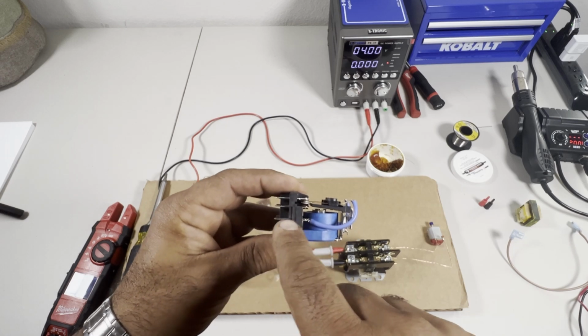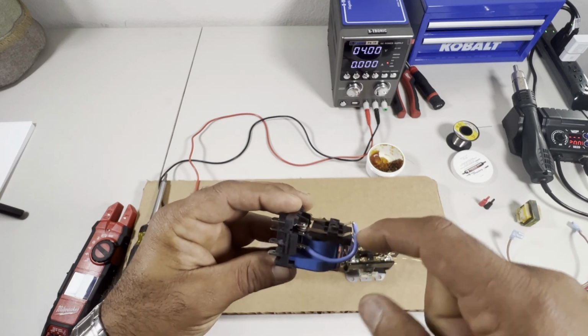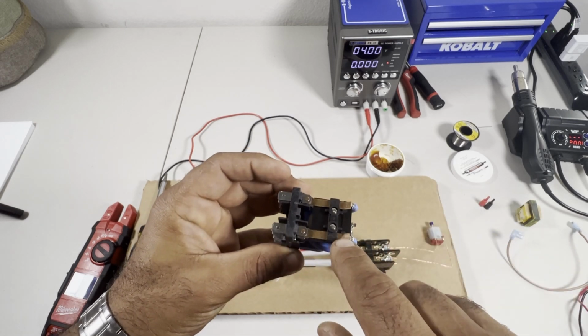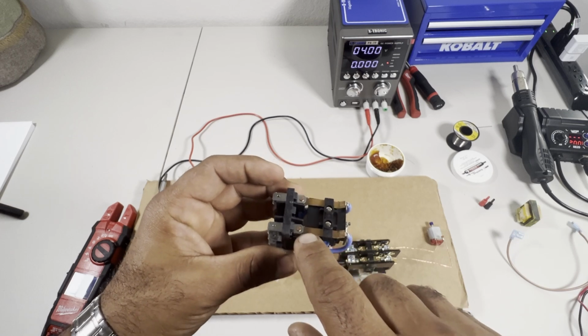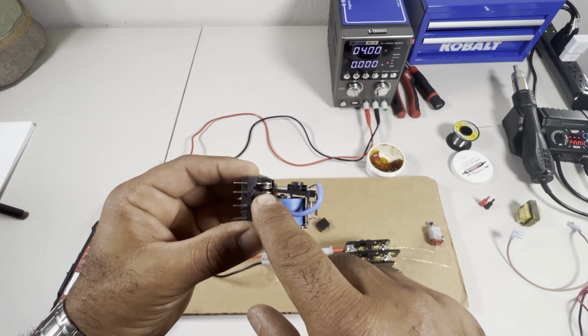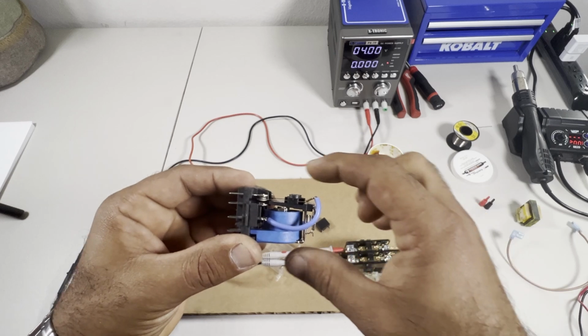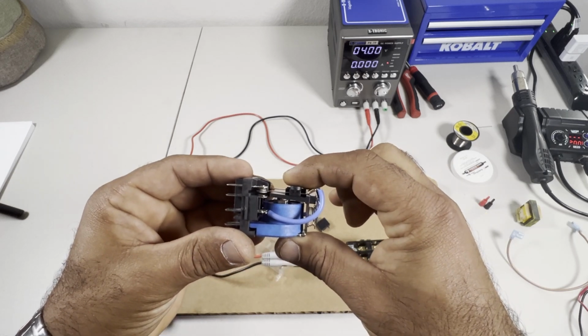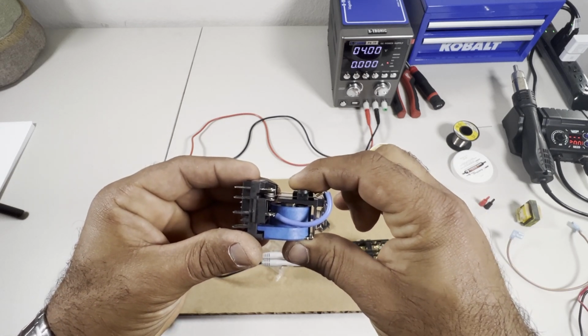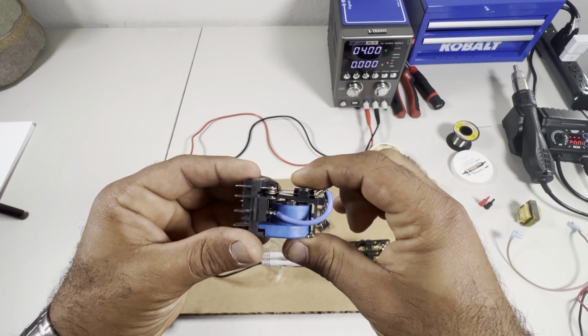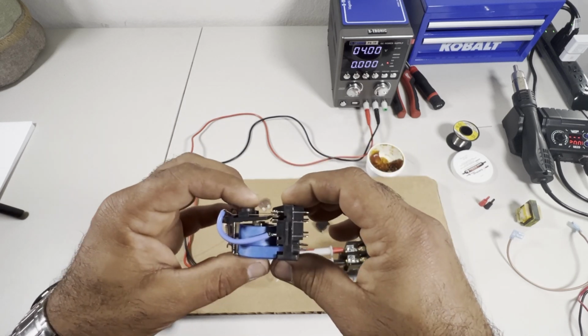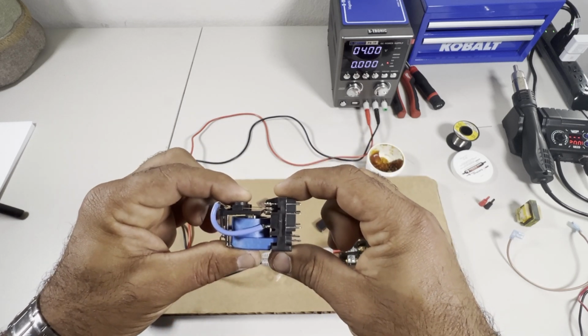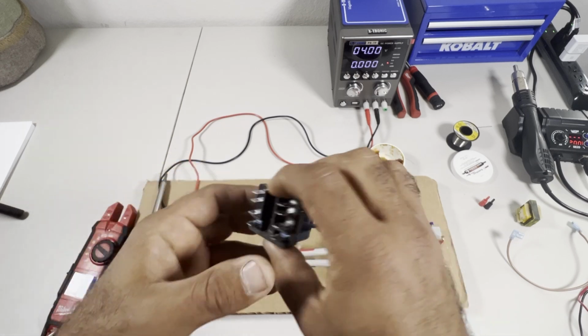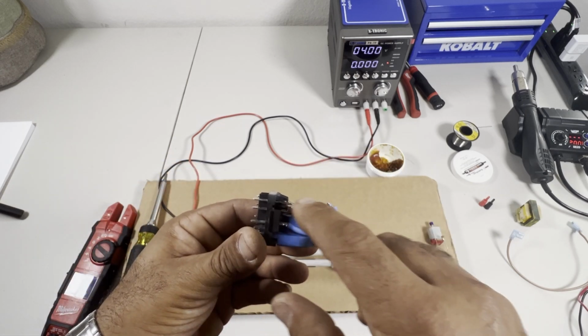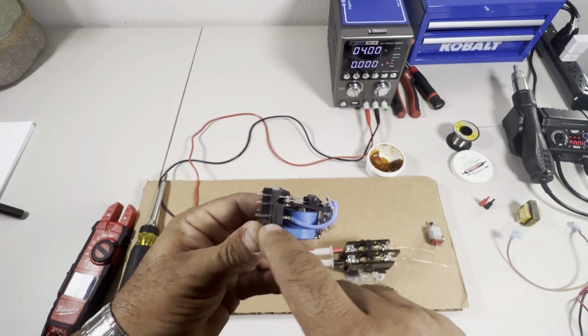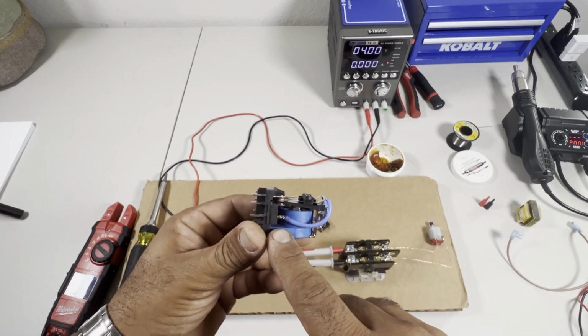As you can see, there is a wire. It comes all the way up here and connects to this spring. This spring has a little point of contact right there. And you can probably see this is moving. This is going up and down. It has two sets of these. This relay has normally closed and normally open contacts.